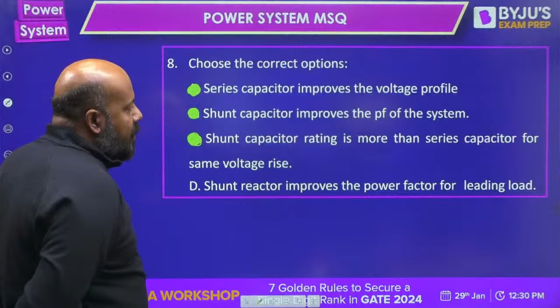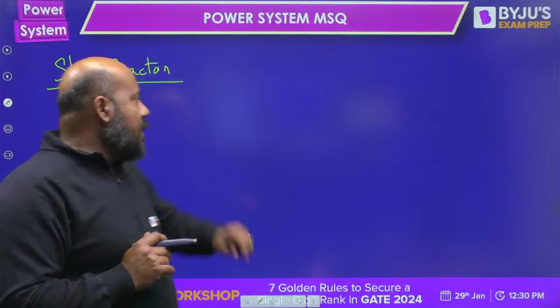Option D: shunt reactor improves the power factor for a leading load. Everybody must be 100% sure that if it is a lagging load condition, then the shunt reactor will always deteriorate the power factor, reducing it. Now let us understand the leading load case.